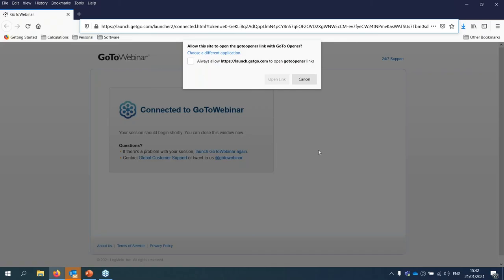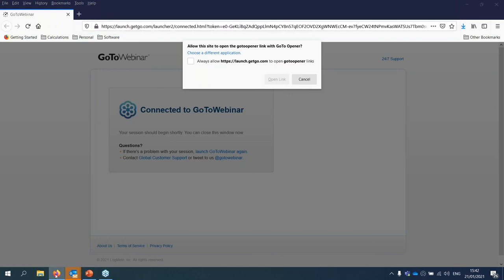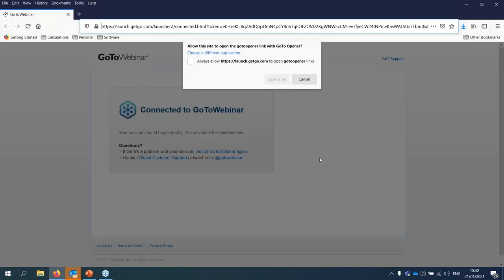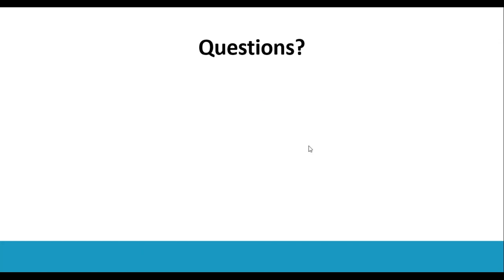Thank you very much. That was a fantastic session. The first question, from Mohamed Abbas, asks how do we know when equilibrium is reached? This is a very good question. In the gravimetric method, we use a mass equilibrium criterion. When performing adsorption measurements, we define a change in mass criteria — specifically, if the change in mass is below 0.002% per minute for a duration of 10 minutes, then the software automatically moves to the next step. This is how we define the mass equilibrium criteria for the adsorption experiment.